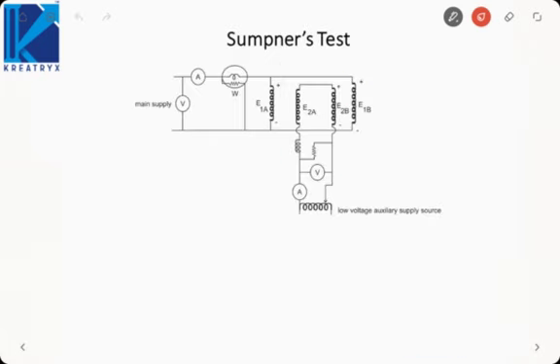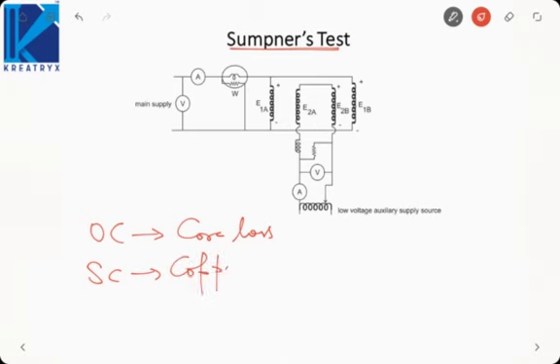Next is something called Sumpner's test. When we were performing the open circuit test, we were encountering core loss and copper loss was negligible. In the short circuit test, we were encountering copper loss and core loss was negligible. That means in both these tests we are encountering only one of the two losses, but not both.